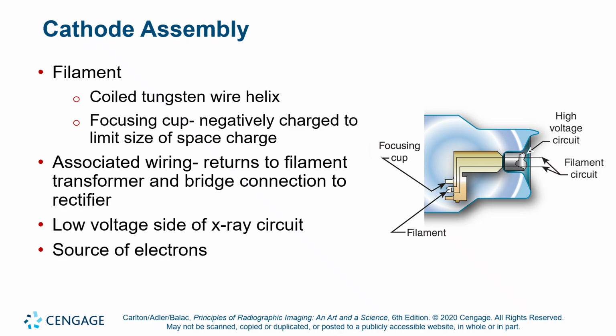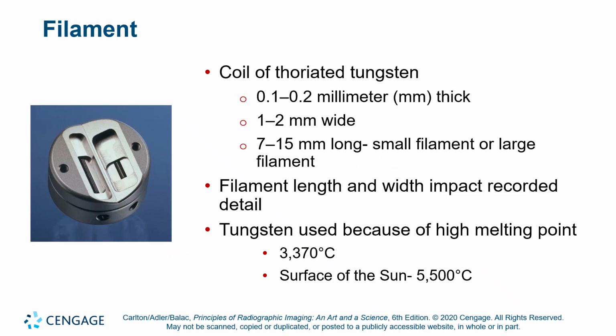Typically, the filament circuit is low voltage operation until the moment of exposure. So heating up the filament is low voltage, high amperage. Okay. It's the high amperage that triggers the thermionic emission. Okay. So here we have a picture of a filament that's been removed from an X-ray tube, and you can see that both of those filaments effectively sit at the bottom of a bathtub. That's the focusing cup.